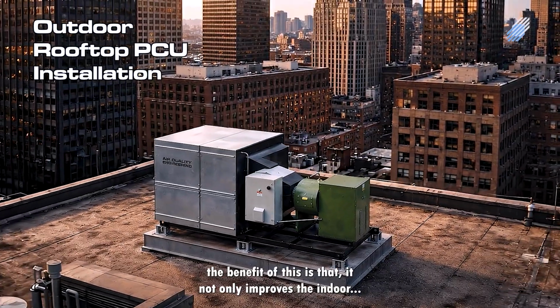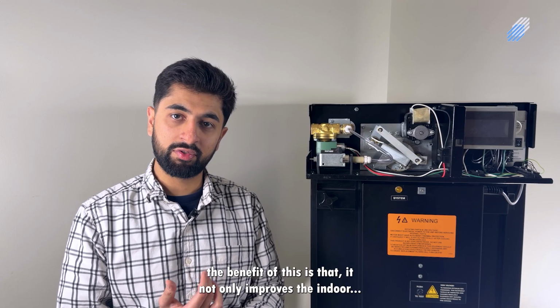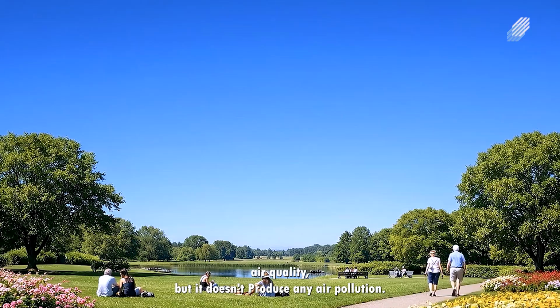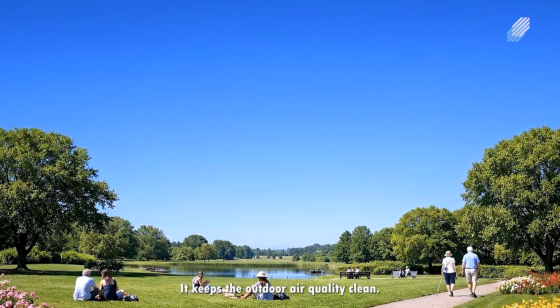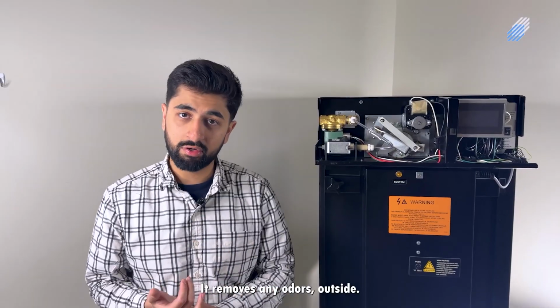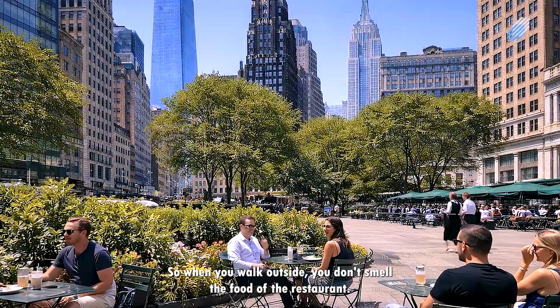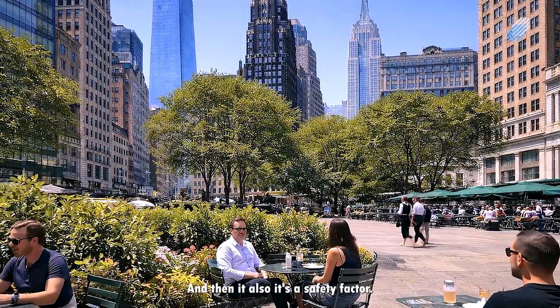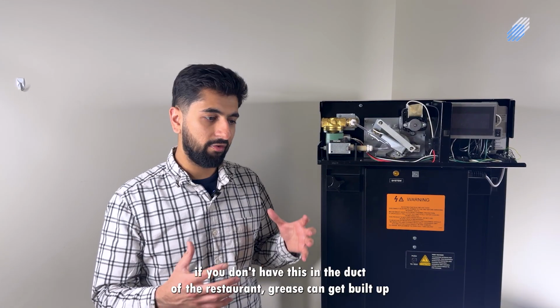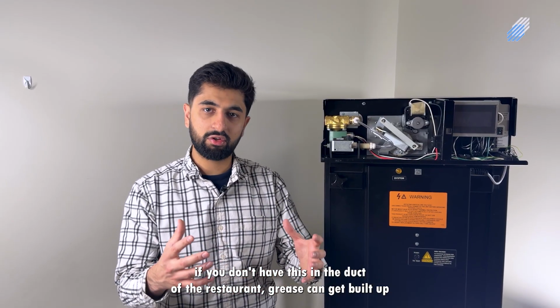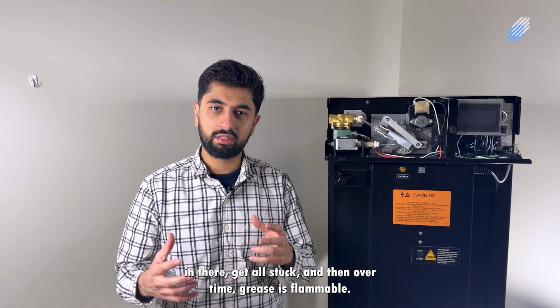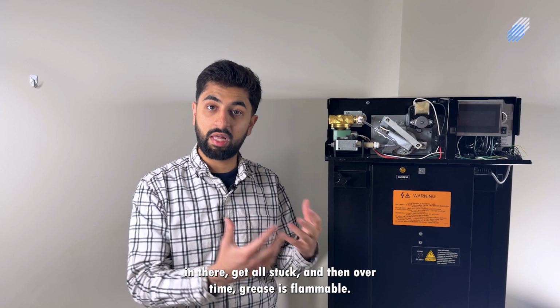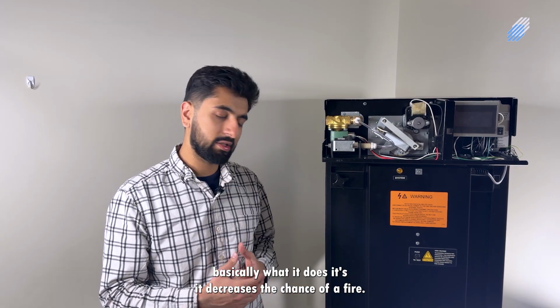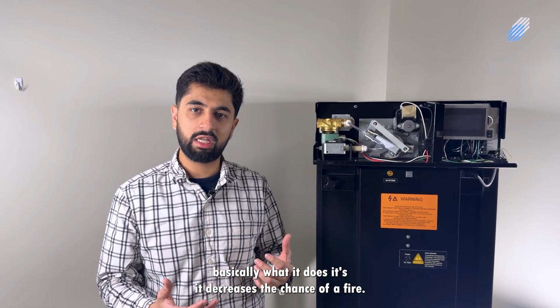The benefit of this is it not only improves the indoor air quality, but it doesn't produce any air pollution. It keeps the outdoor air quality clean. It removes any odors outside, so when you walk outside, you don't smell the food of the restaurant. And then it's a safety factor. If you don't have this in the duct of the restaurant, grease can build up in there and get stuck, and grease is flammable, so over time it can cause a fire. Basically, it decreases the chance of a fire.